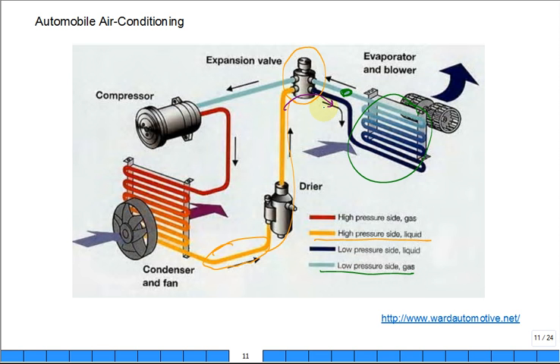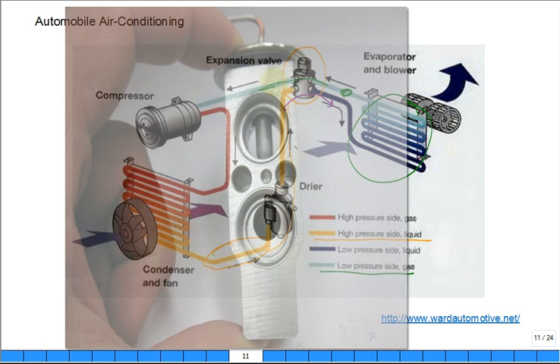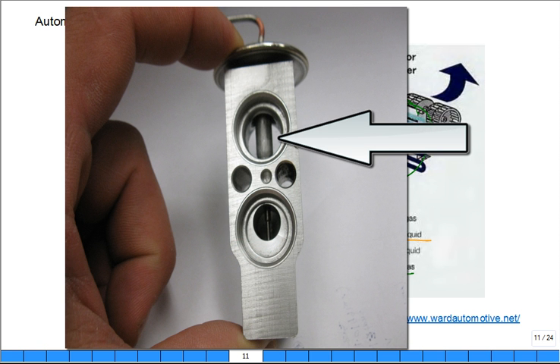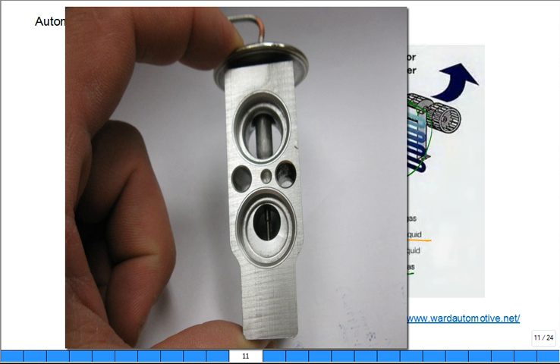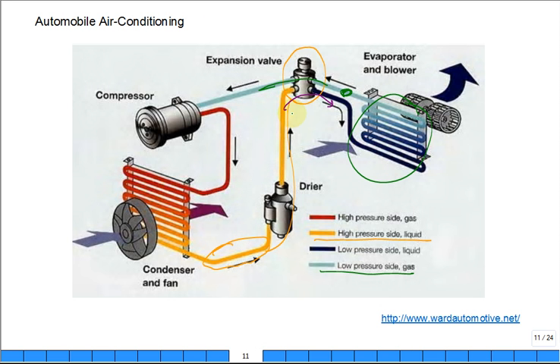And so it's low pressure vapor going through. There's a bulb right here in the middle. It senses the temperature of what's coming off the evaporator. It will then lift or push down a needle which will modulate the flow in the lower two parts of this block. It'll modulate the flow of the liquid into the evaporator. It'll control this flow rate by opening it or closing, pinching off, because you don't want to flood the evaporator or starve the evaporator. You want to give it just the right amount based on the temperature coming out of the evaporator.